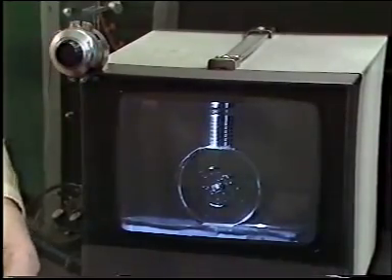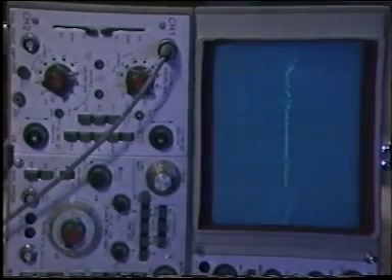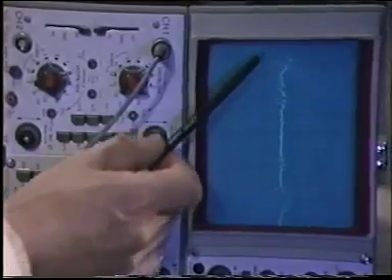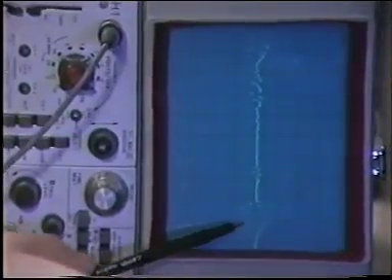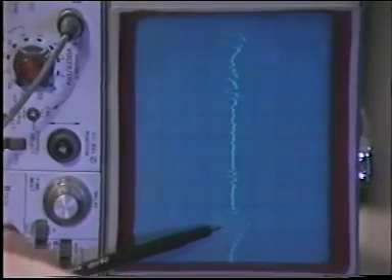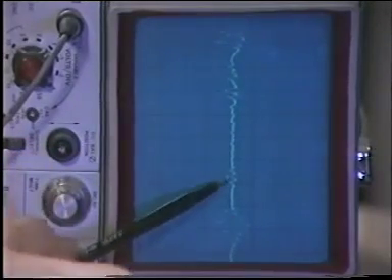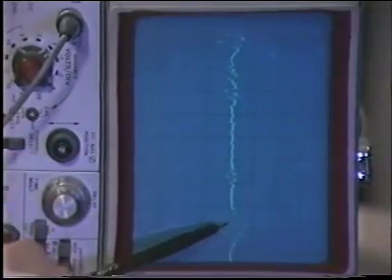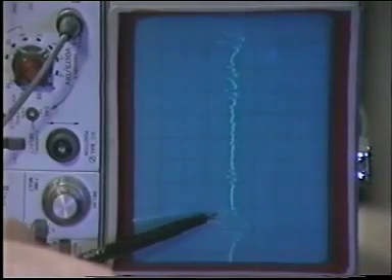Let's look at the actual waveforms on the transducer. Now, on this oscilloscope, you can see at the top here is the transmitter waveform, and down the bottom is the waveform that the transducer receives and converts back into an electrical signal from the bottom of the block. There are one or two other echoes in there from some of the defects in the block. Now, to remind you of where this signal comes from, we'll look back at the waves again.